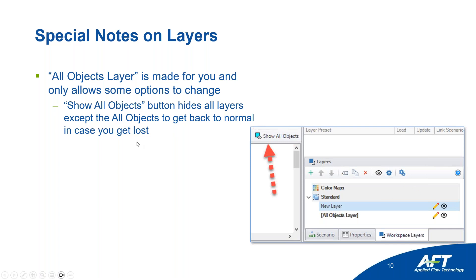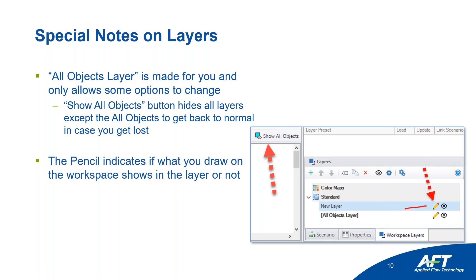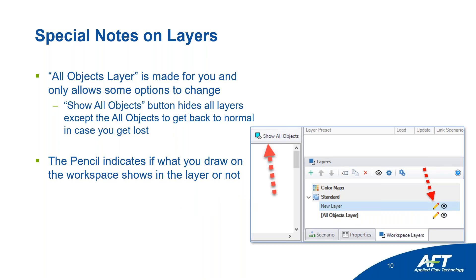Some special notes: the all objects layer has limited edits. If you get lost — you've made a bunch of layers and don't know what's actually in your model because you're hiding things — press the 'show all objects' button. It turns off all other layers and shows just the all objects layer — it's a way to get back home. The pencil indicates whether what you draw on the workspace will be added to that layer. If the pencil is on and you drag a pump onto the workspace, it will be attached to that layer.